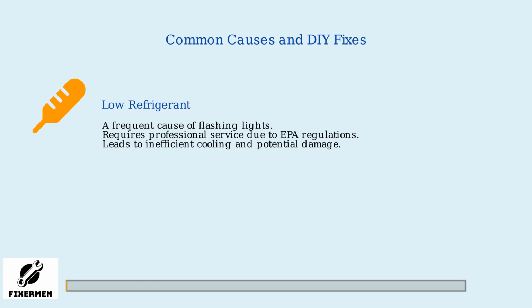Several common issues can trigger flashing lights on your Rheem AC unit. Let's explore the most frequent causes and whether they require professional help or can be fixed at home. Low refrigerant levels are a common culprit behind flashing lights. This happens when there's a leak in the system, reducing the amount of refrigerant available. However, handling refrigerant requires certification under EPA regulations, so this must be fixed by a professional technician.